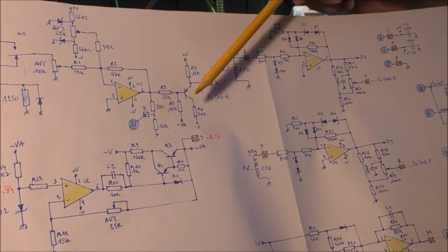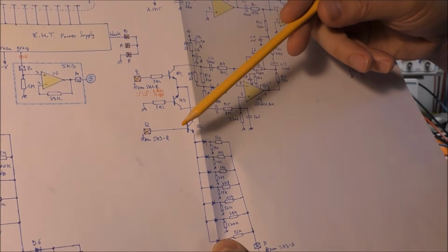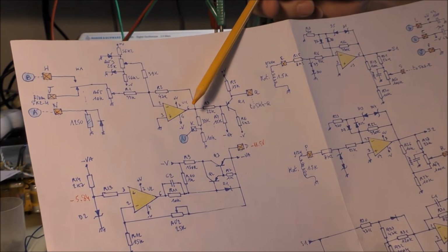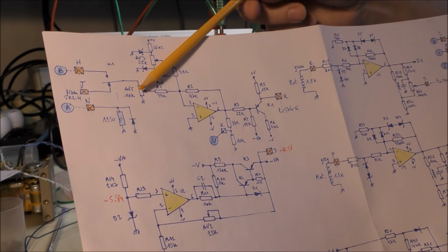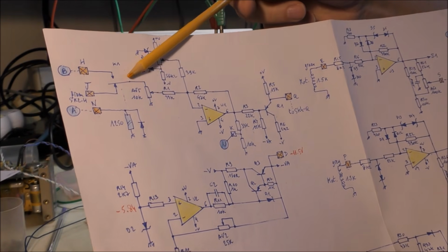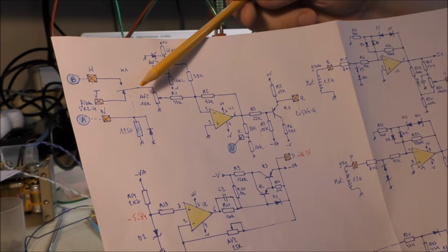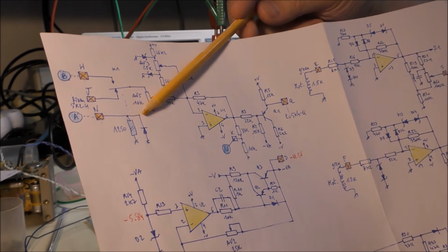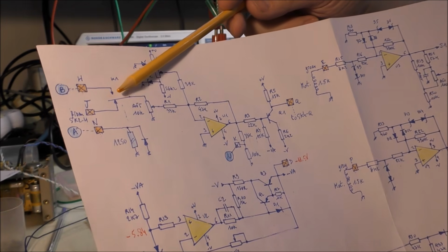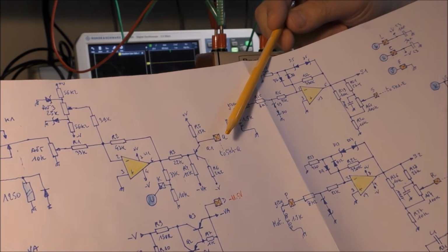It is this circuit here, so we can see that there is a PNP transistor here. This VBE voltage compensates the VBE voltage of Q2 here. We can see that there is an inverting amplifier here, there is an offset adjustment, and the input of this amplifier is connected to this relay. This voltage can be connected either to one pin of the connector, otherwise it is connected to another circuit. I have activated for the moment this relay, so therefore it is possible to apply a voltage. This voltage should be negative, because at the output we should have a positive voltage for the multiplier.